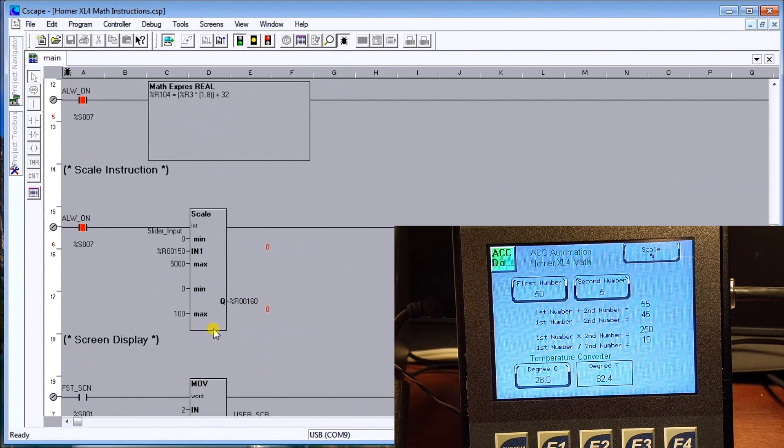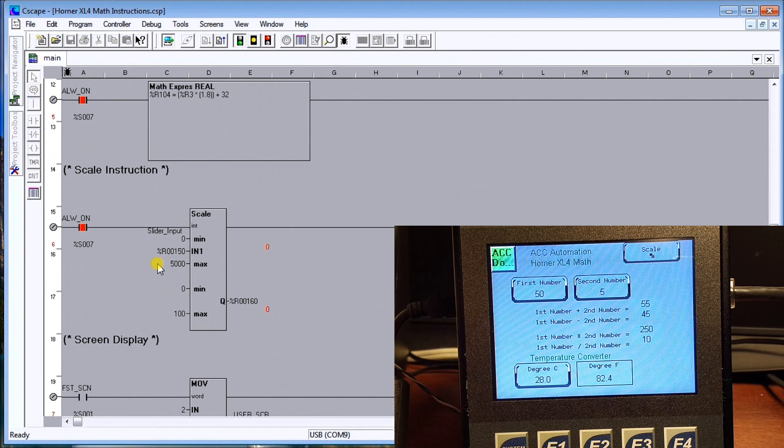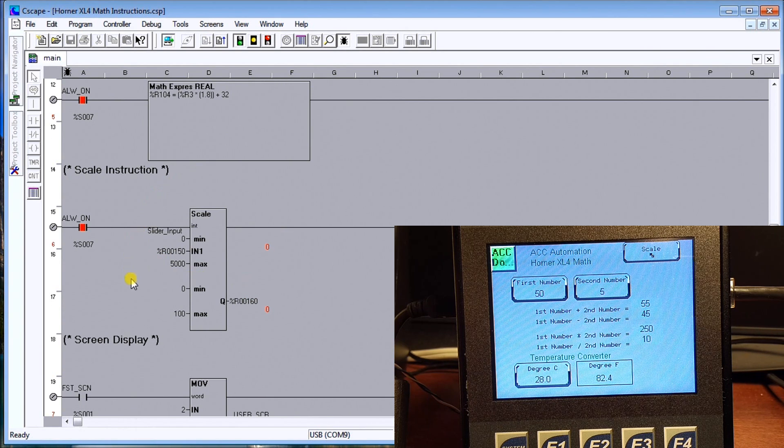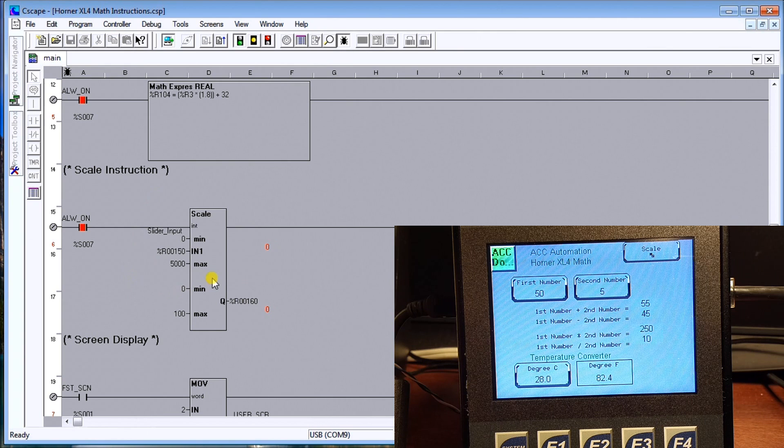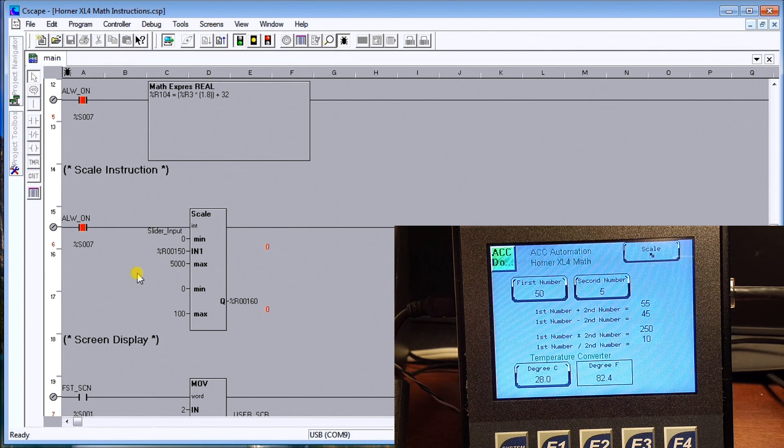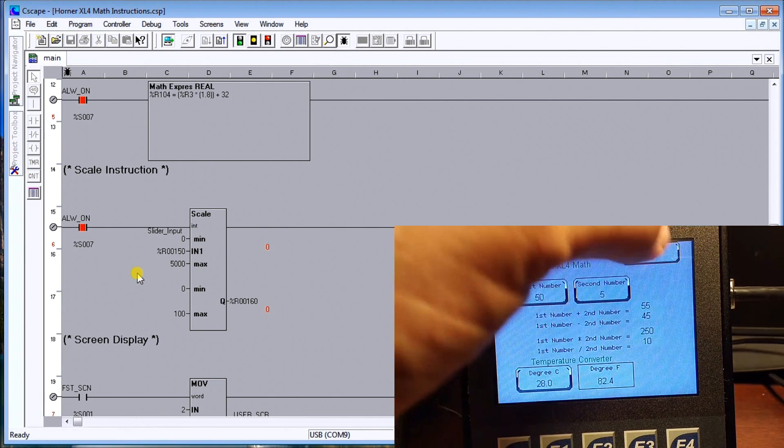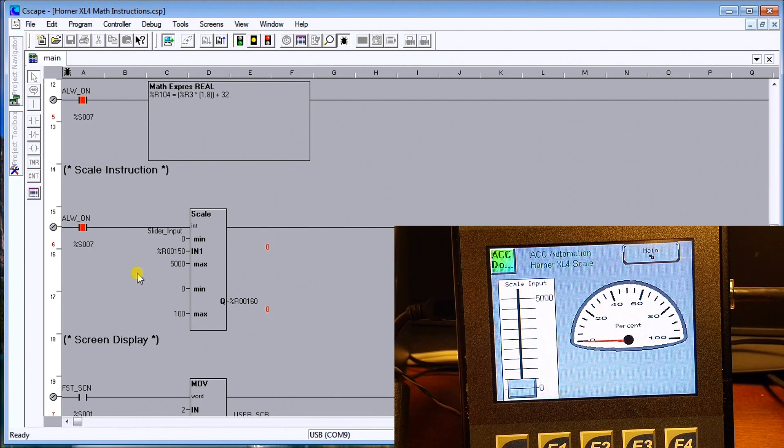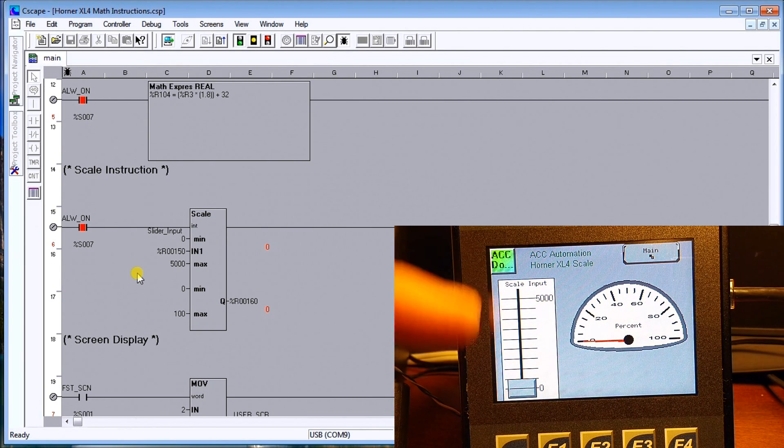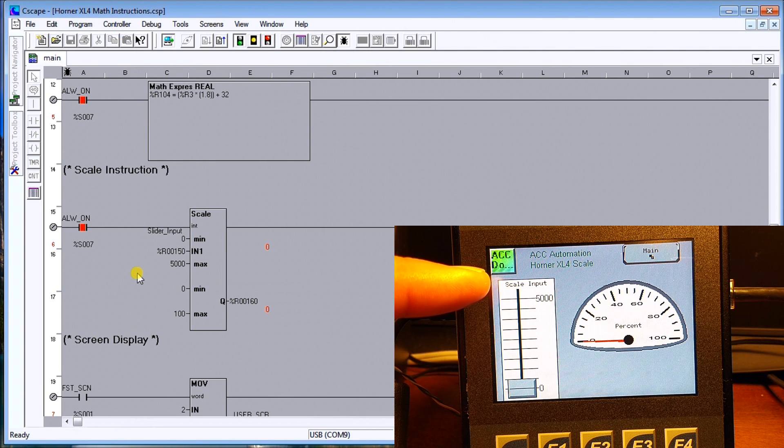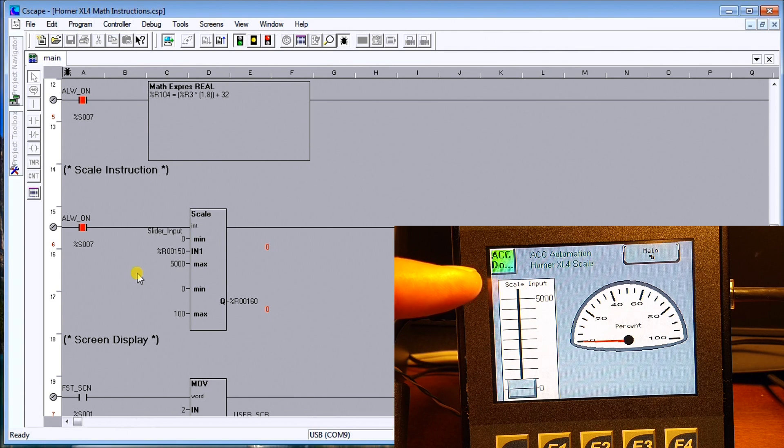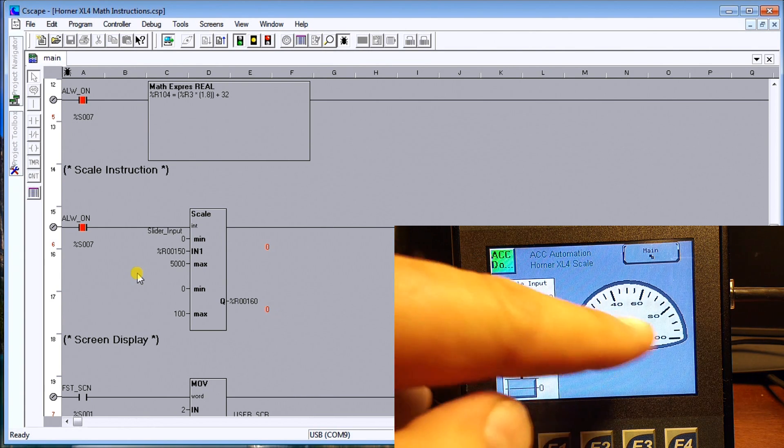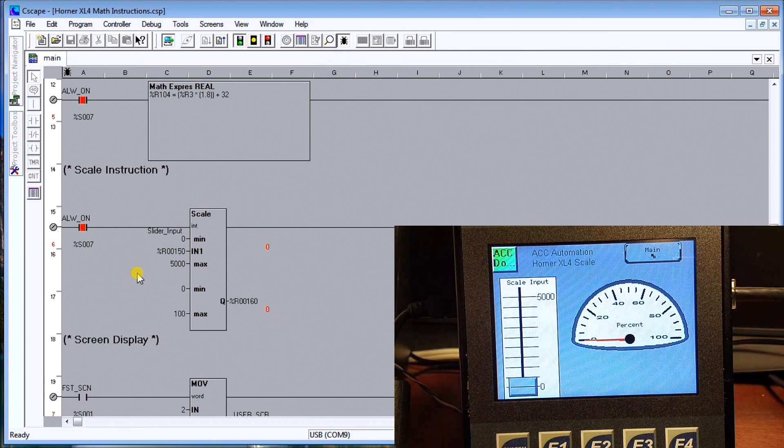Now the last one we want is scaling and the scale feature basically will take a value in a range in - it's called the screen. So in our case here we're going from zero to five thousand and we're going to convert that to zero to a hundred in order to give me a percentage.